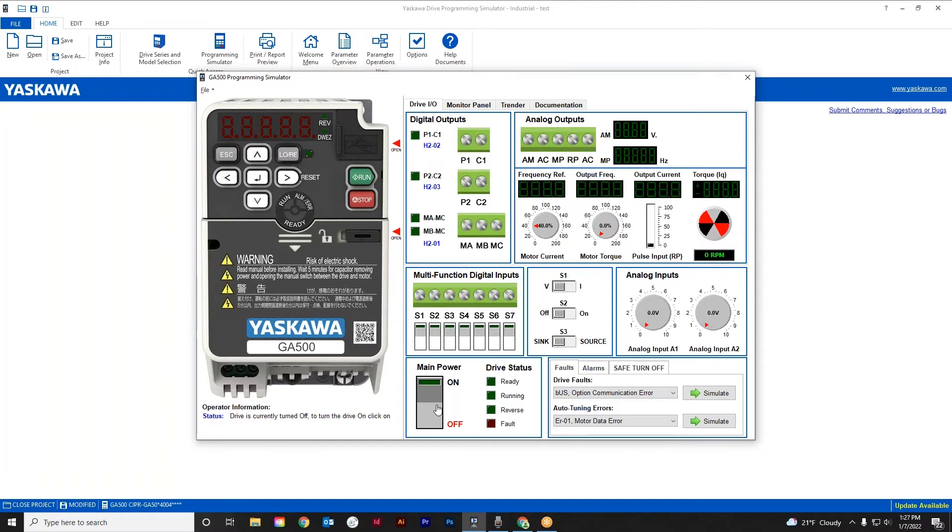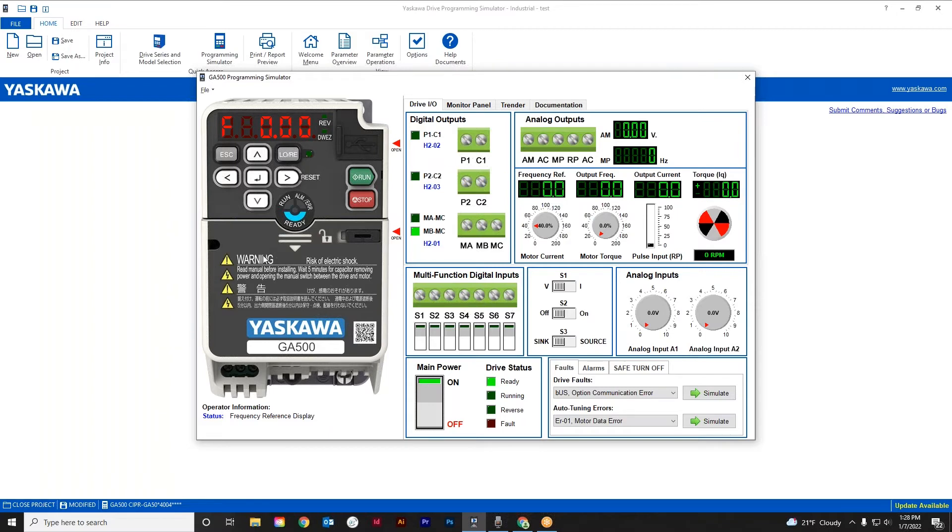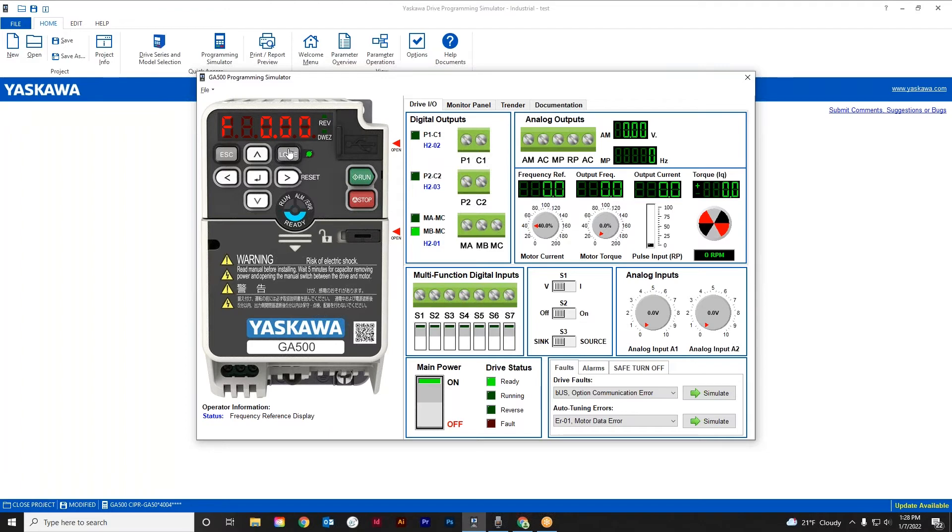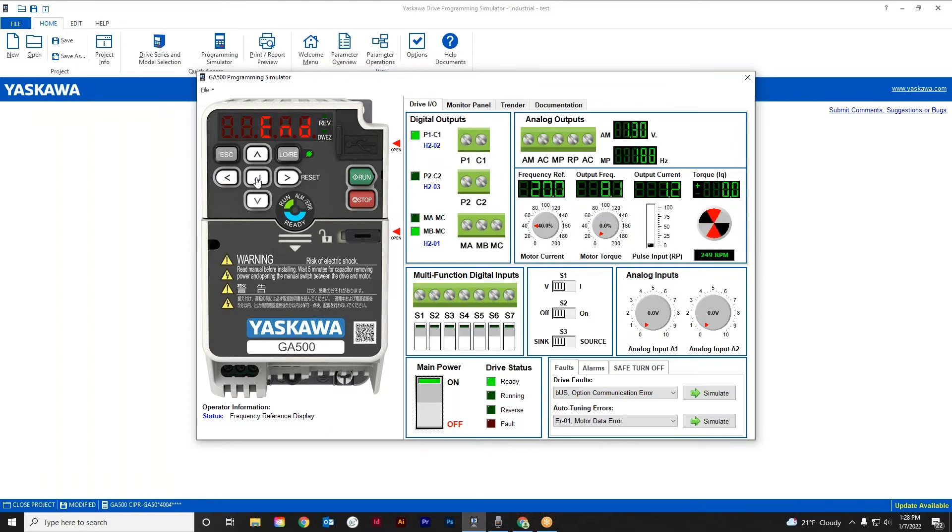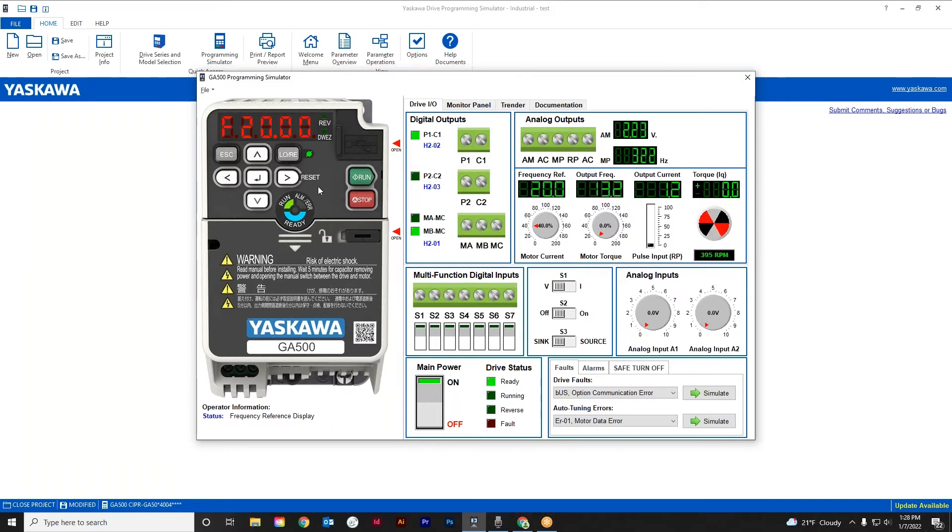So let's get started. What's nice about this is that it has a power switch. So obviously just like any other drive, you have to turn the power on. So let's do that. Turn the power on. And that's what the drive looks like out of the box. Obviously this is a programming exercise today, but this is what the screen looks like when it's out of the box. This is what's called the home screen or the F screen is what we say during training. And so this is a normal look to the drive. A few of the keys here is an escape key. We'll talk about that when we get into the programming. But here's a local remote key as well. So if you want to run it from the keypad, you can do that just like you would if you had the drive in front of you. So here we can hit the run key. We can see the little run light blink. We can give it a speed reference. And we'll see that the motor over here is starting to turn. So again, just like if you're in front of the drive. We'll stop it and we'll go back into remote.